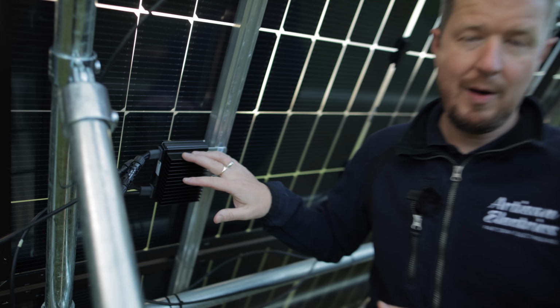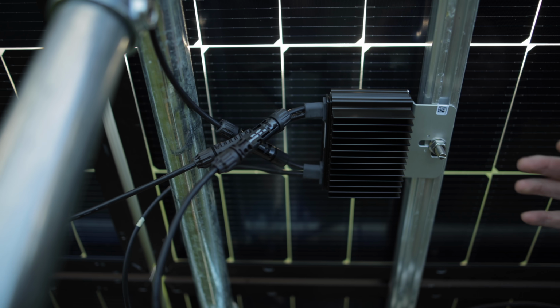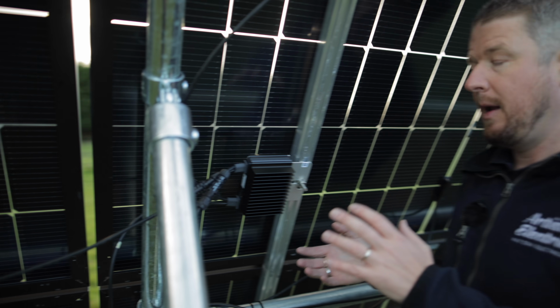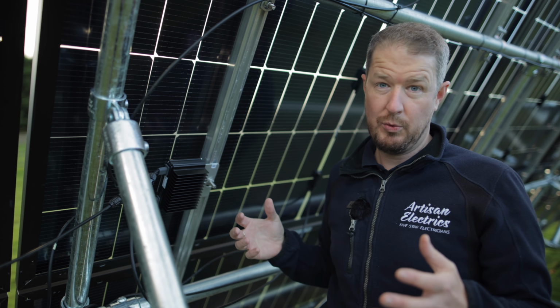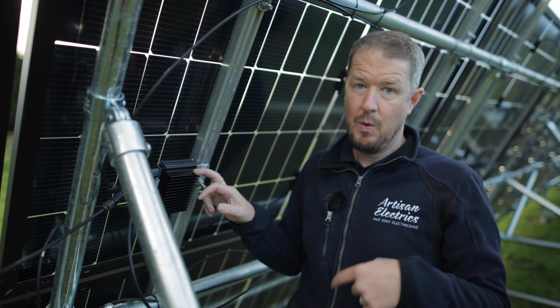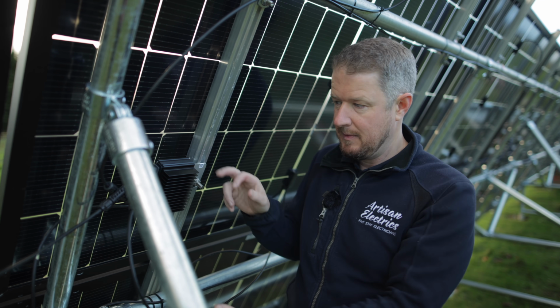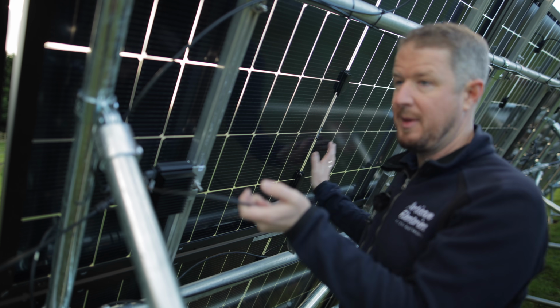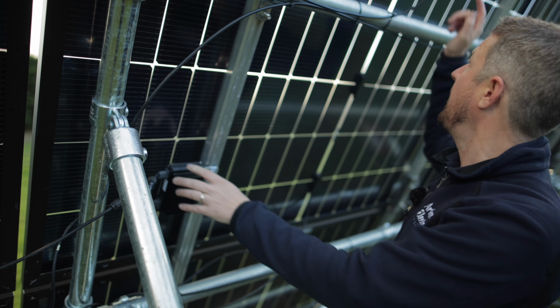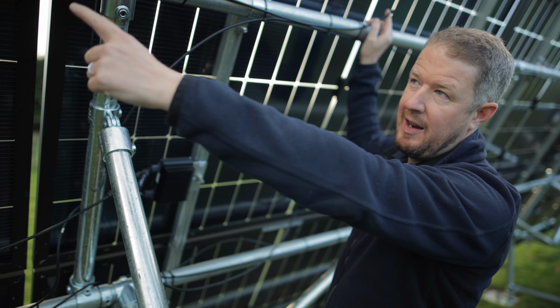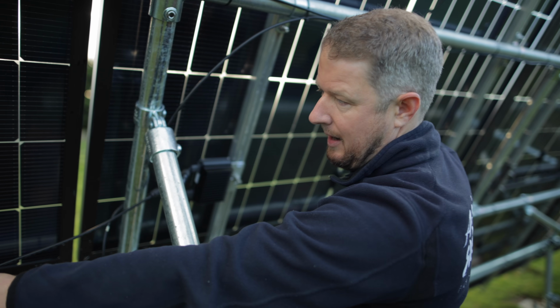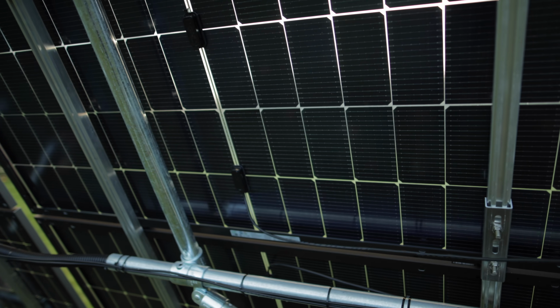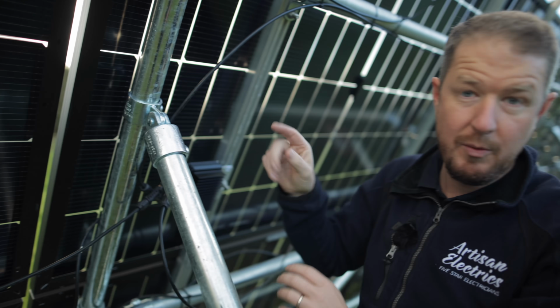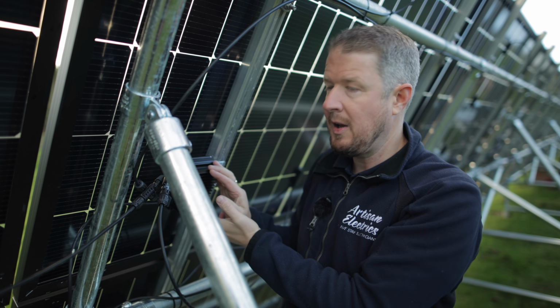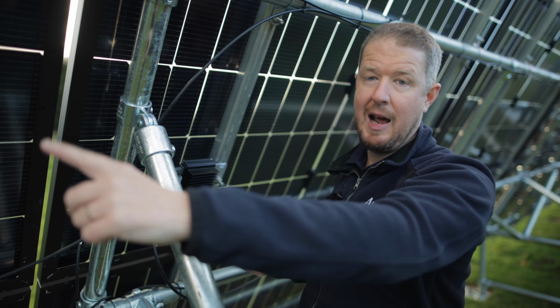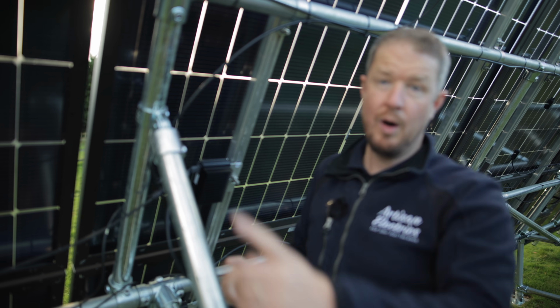These are S1000 optimizers, meaning they can take up to 1,000 watts of DC power into them. Essentially that means we can string 2 panels into one optimizer, so they work in series. The positive from this panel goes into the optimizer, then the negative from this panel loops into the positive of the next panel, and from the negative of that next panel it goes back into the optimizer. So it's a little circuit with 2 panels on one optimizer, and each optimizer connects into the next one to create a whole string of optimizers.